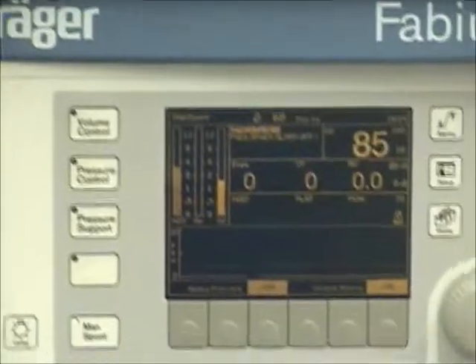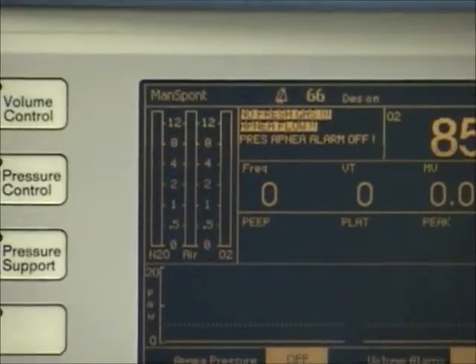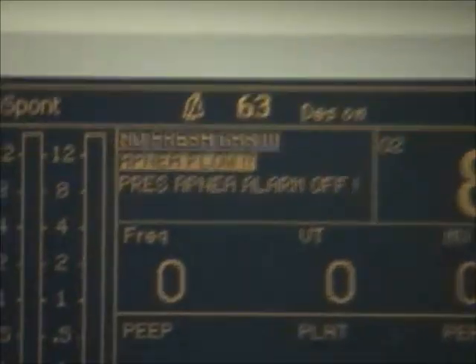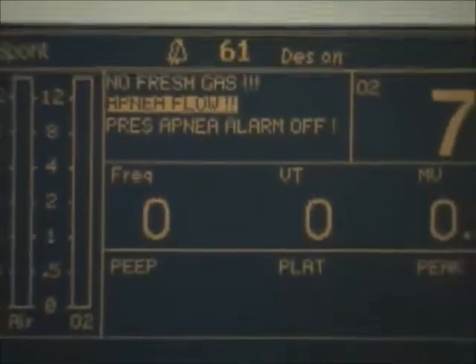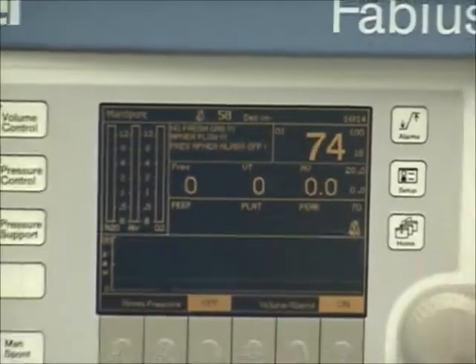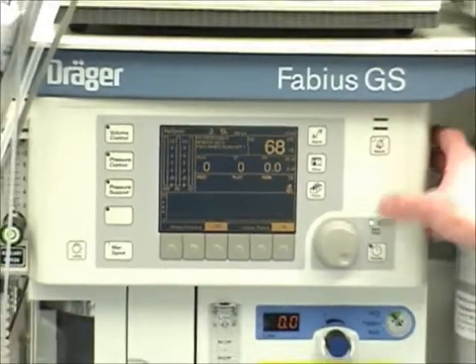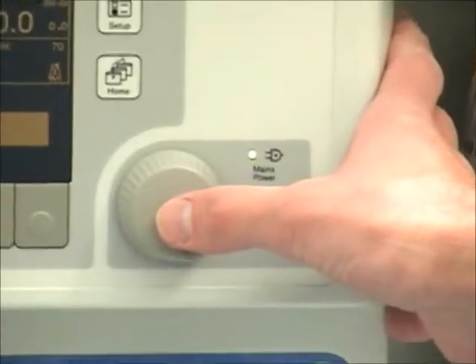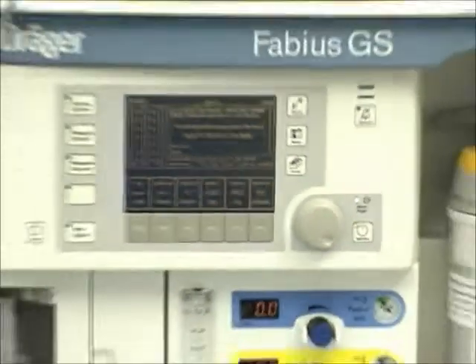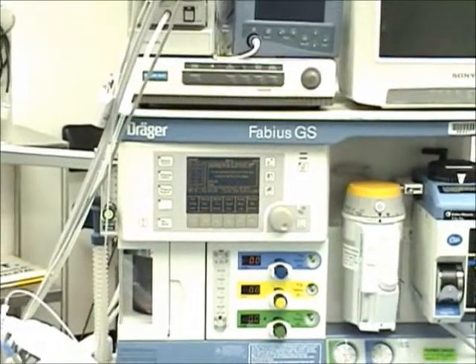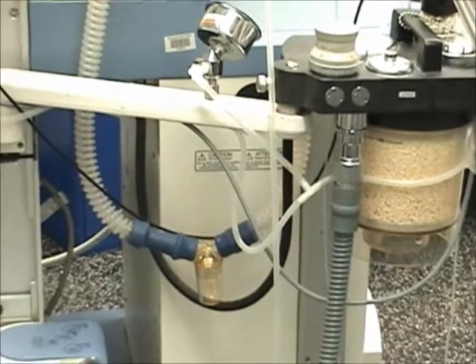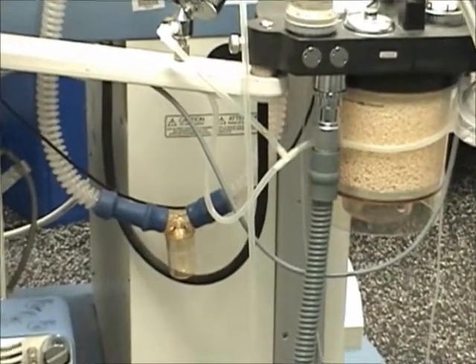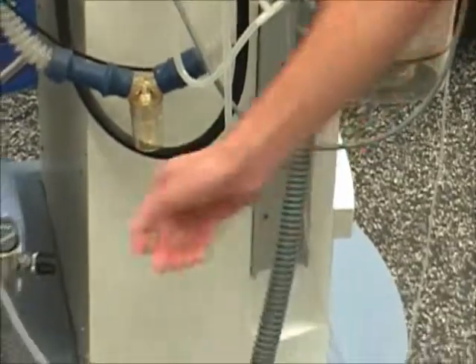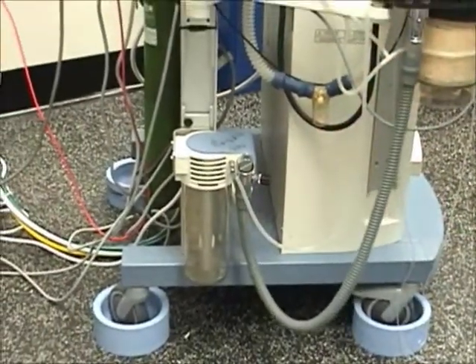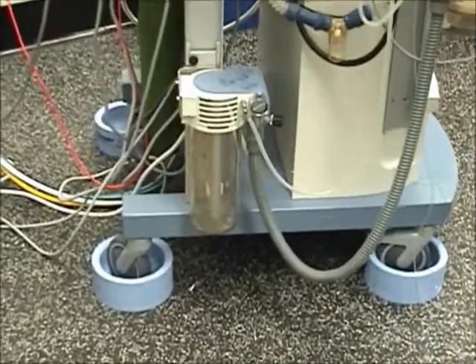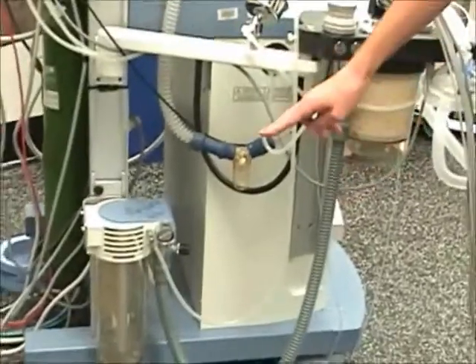Close the oxygen metering valve. This should also discontinue the flow of nitrous oxide. Now close all metering valves. An alarm will sound indicating there's no gas flow through the circuit. Press the standby soft key and confirm the selection by pressing the rotary wheel. Adjust and check the scavenging system by ensuring a proper connection between the scavenging system and the APL valve. The ventilator relief valve and the APL valve share a single hose to the scavenger.